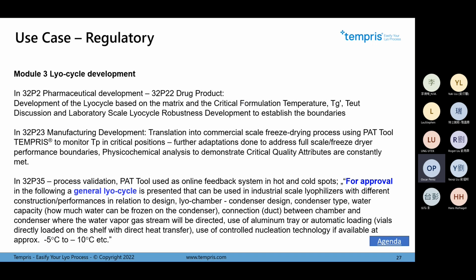We close the door. We have silicone oil going through the shelves. We have a vacuum or Pirani measurements, but this is not enough to see exactly what's going on inside the vials. In every vial it's not possible, of course, but it's possible to control in these critical positions.